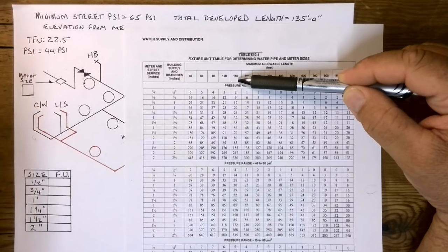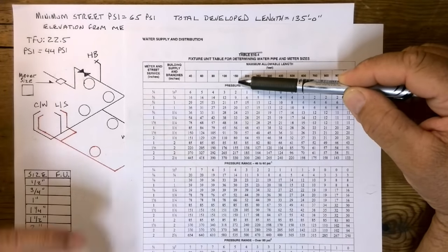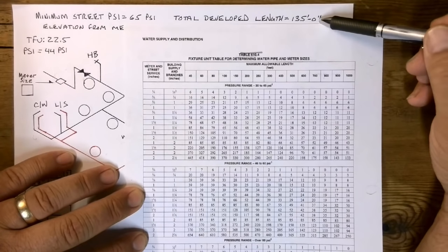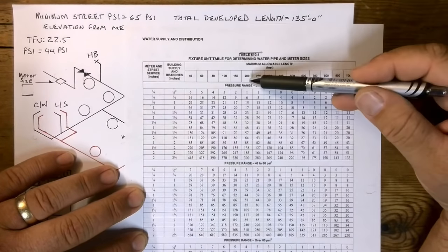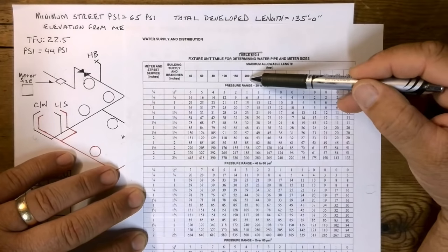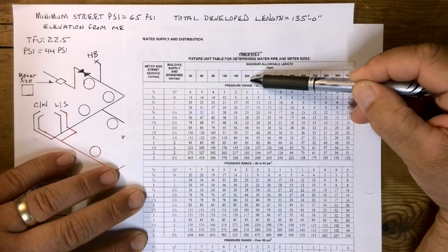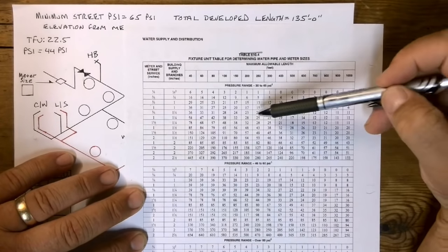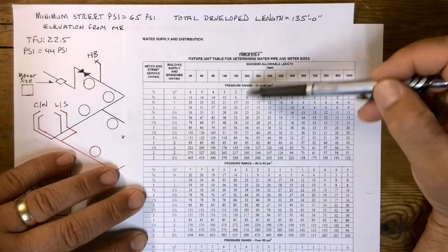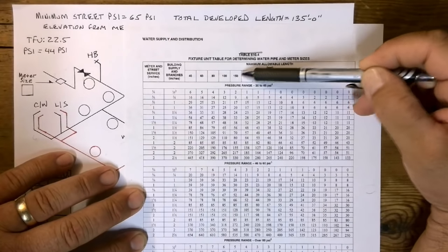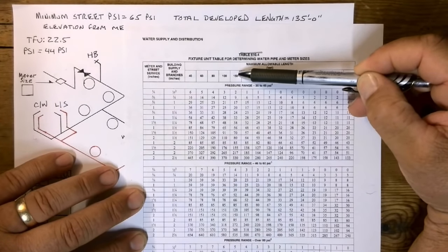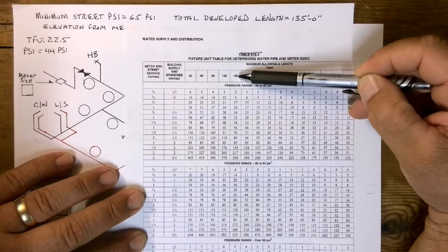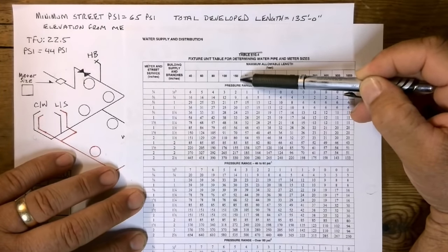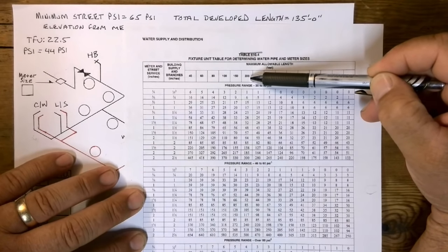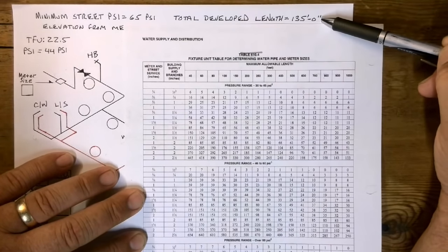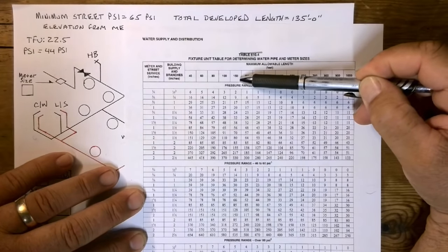So we're going to size it based on 150 feet. I'm going to tell you that if this was 151 feet, you will not size it at 150 feet. You will take it to 200 and size it at 200. I'm telling you that because that is what the code requires. There's no fudge factor. So 151 feet takes you to 200. Fortunately for you, I put 135, which is easy. We're putting it at 150.